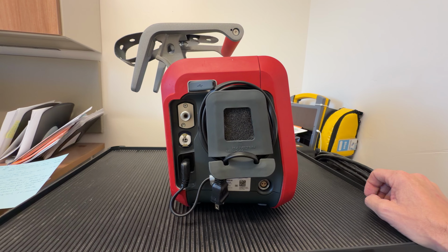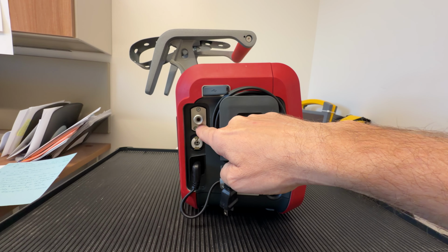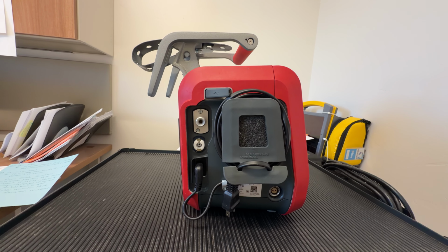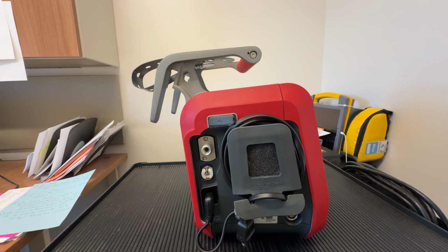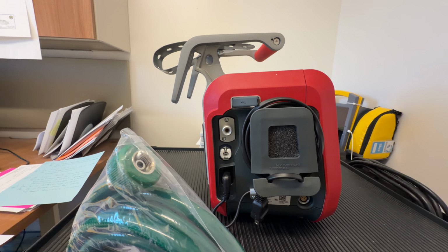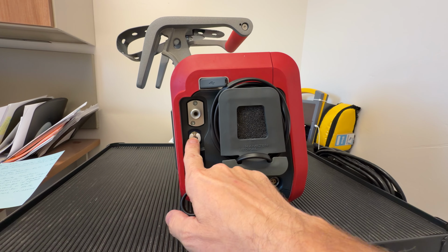All right, moving on down, this is your high pressure oxygen connector. This accepts both the DISS, the diameter index safety system, or the NIST inlet fitting. So this is going to be that standard high pressure. Typically, we're going to be using the DISS high pressure tubing. So this would connect to the adapter on your oxygen source, your oxygen tank, and then that would connect to the ventilator. In addition to that, the ventilator can also provide low pressure oxygen. So if you do not have a high pressure source, if you have the adapter for this ventilator, you can plug it into the low flow port on your oxygen source and bleed oxygen into the ventilator as well. And that's where you do that on this ventilator.